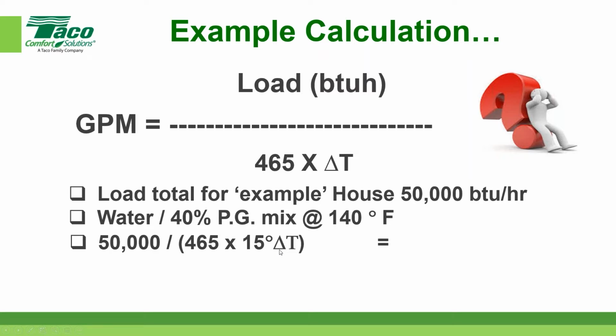Let me expound a little bit on delta T. A lot of people think that it's always 20 or it's always 10, but it's not. It's a variable. The delta T will change typically based on what you're doing with the heat emitter. What type of heat emitter is it? That'll normally drive your delta T. And that applies to radiant floor, panel radiators, baseboard, fan coil units, all kinds of things. I'm trying to use some oddball numbers just so you don't get used to using one number. So if I take 465 times 15, I'm going to fill that in here as 6975.